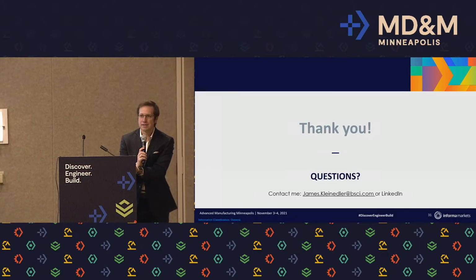And then shipping back devices, if they're just for investigation, if they're just for understanding what happened, they're not going to be used in a clinical trial in the US. You wouldn't have to have an IDE approved to ship those devices back through customs. But if you're shipping capital equipment back or some other piece that's going to be then intended for US patients, then you would need an investigational device exemption prior to doing that. Does that help?